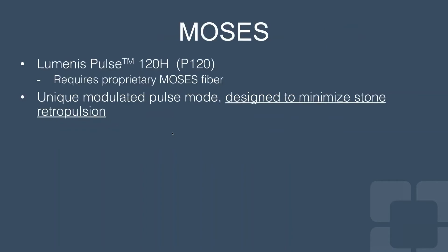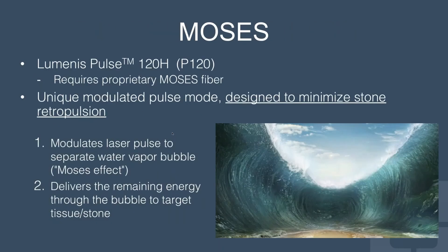Many companies have developed lasers that can modulate pulse width to generate longer pulse widths. Lumenis in particular came up with a proprietary technology known as MOSES, featuring a unique modulated pulse mode designed to minimize stone retropulsion. The mechanism generates a dual pulse: the first pulse is designed to separate the water vapor bubble — the MOSES effect — and the second pulse delivers the remaining energy through the bubble to target the tissue and stone, minimizing retropulsion while maximizing impact.